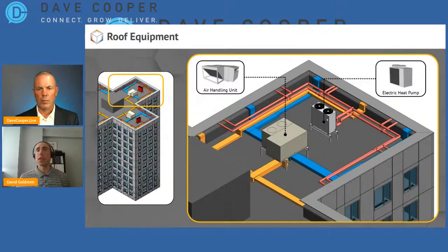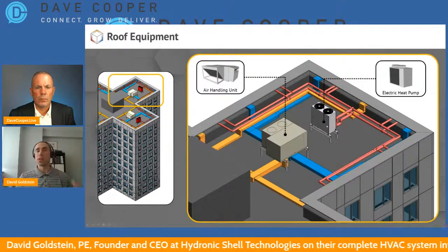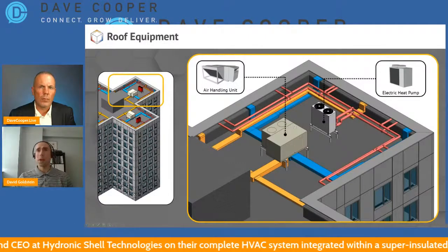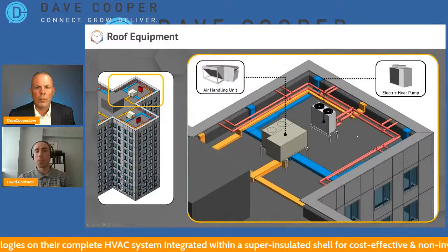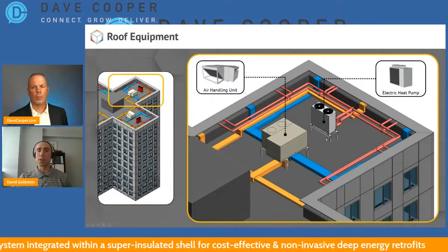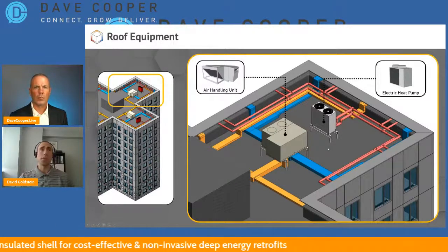The last piece is the equipment on the roof. This is a central HVAC system with central air handling equipment and a central heat pump supplying all the air and water circulated throughout the shell. If we super insulate this building, the loads come way down, so the heat pump doesn't need to be too big. Even in a big building, the capacity needed per apartment, especially accounting for diversity, means a relatively small heat pump, which makes the whole thing manageable. These rooftop units and air-to-water heat pumps are readily available on the market. We're not reinventing anything here, this is off-the-shelf, standard equipment that can be used to supply this system.